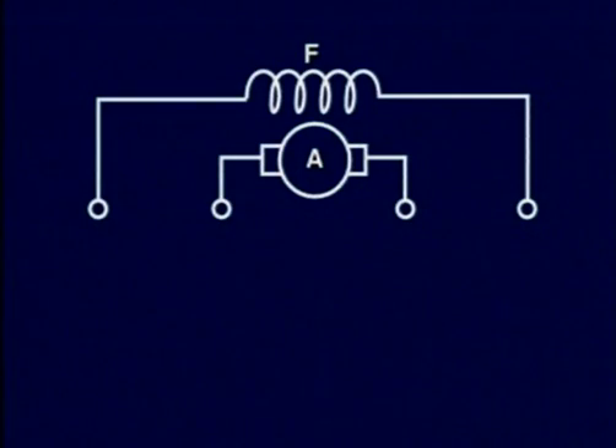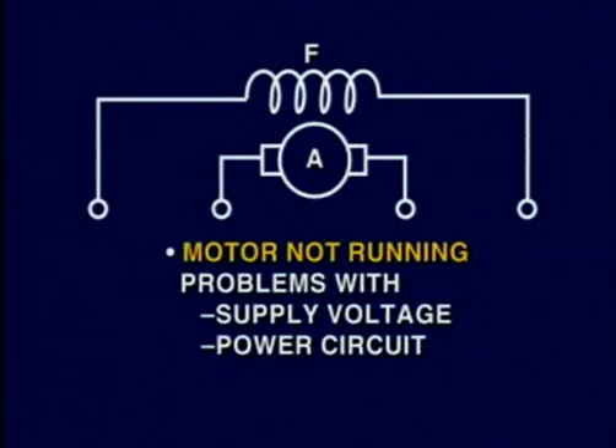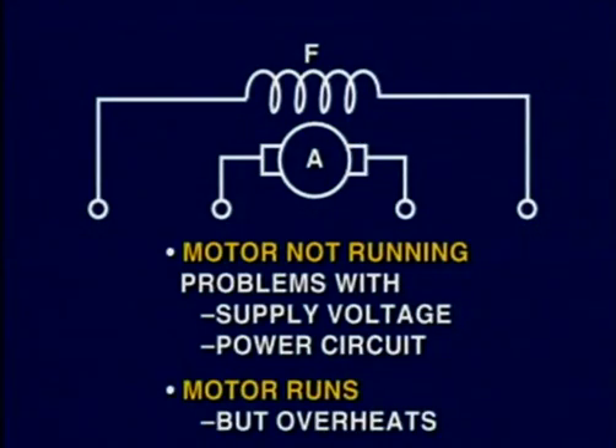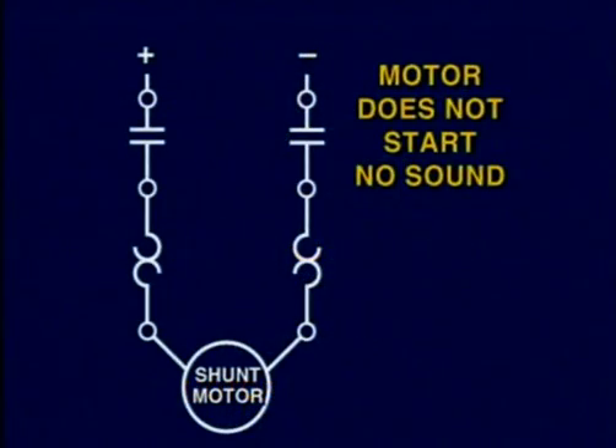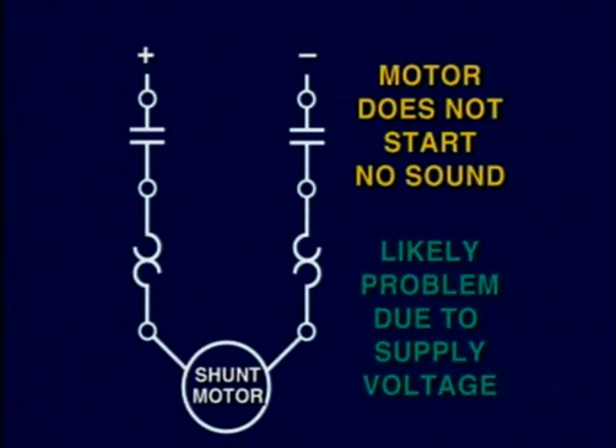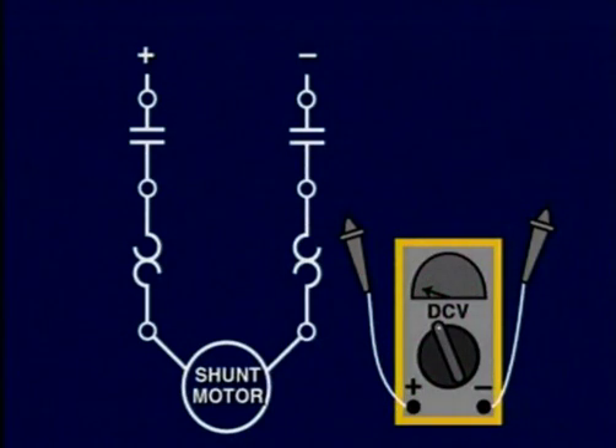The two main problems occur when the motor is not running, in which case it could be the supply voltage or its power circuit. If the motor is running, overheating can be exhibited by the motor, thus indicating a potential problem. If the motor does not start and does not make any sound, it is most likely due to a problem with a voltage being supplied to its terminals. Check for a voltage and troubleshoot the power circuit in the same fashion used for the series DC motor power circuit.